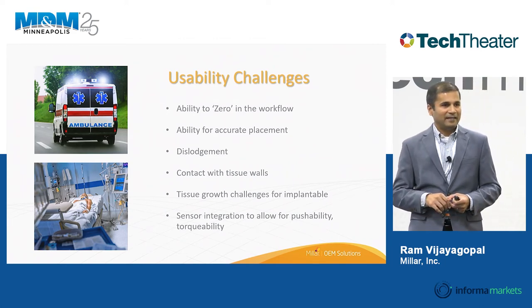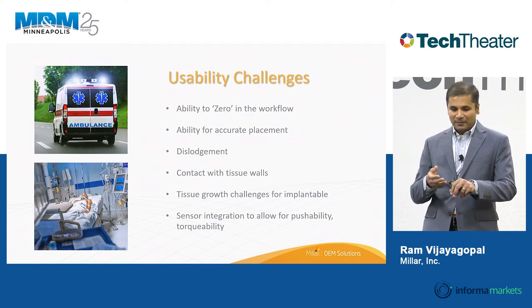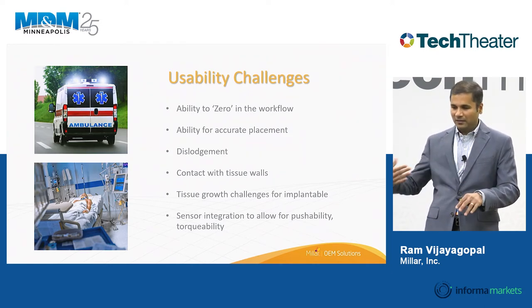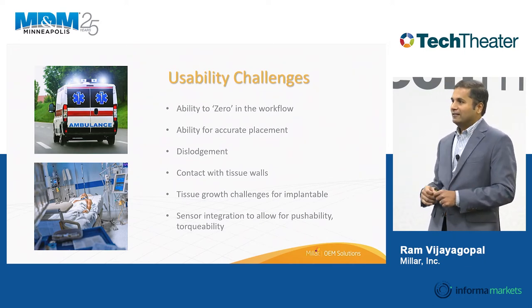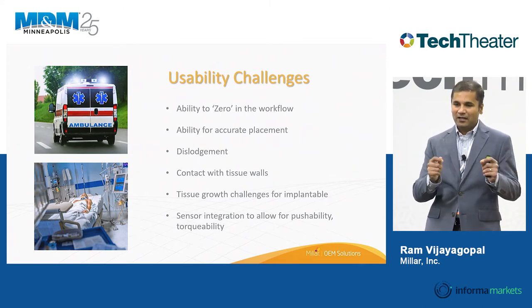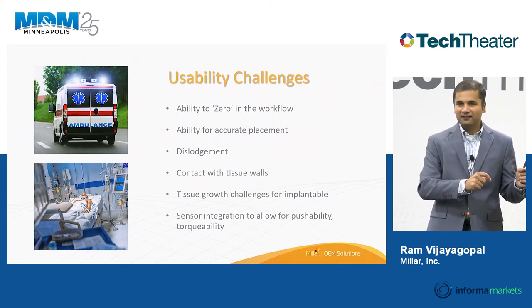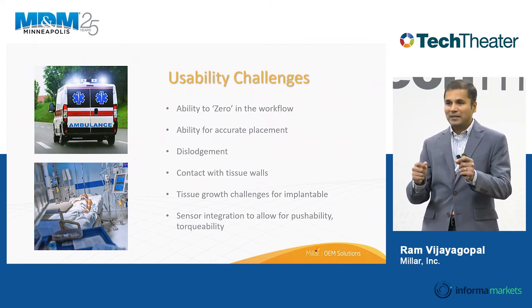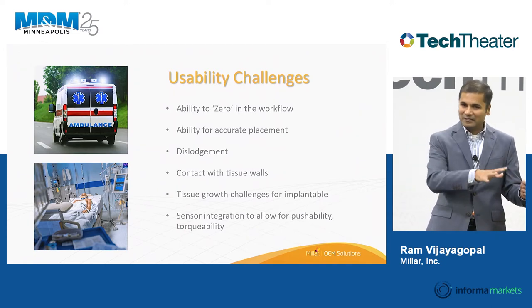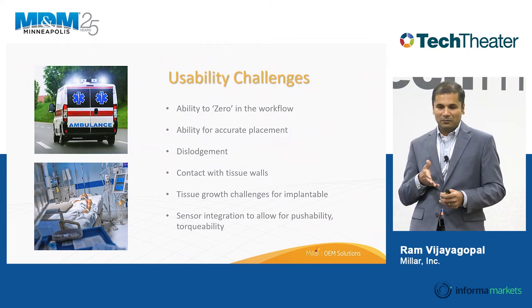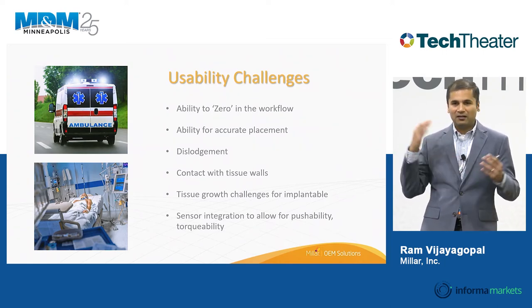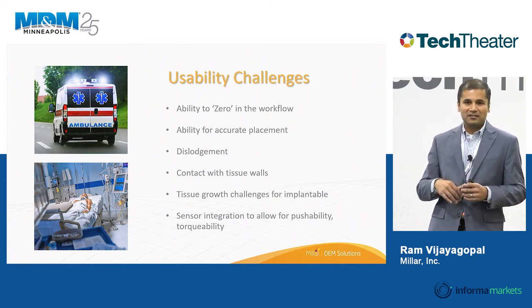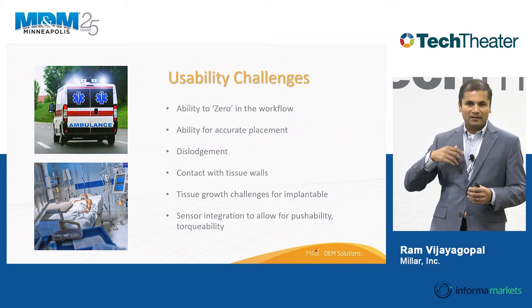Once a sensor is built into a catheter, can it be placed accurately? The designer might intend the sensor to face upward, but the physician may deploy it differently. These devices often get used differently from how they were designed, by people entirely different from those who designed them. Dislodgement is also a concern — if a sensor is navigating a bend in the heart and staying there for three weeks, it will experience many heartbeats. Is there a risk of the sensor popping out?